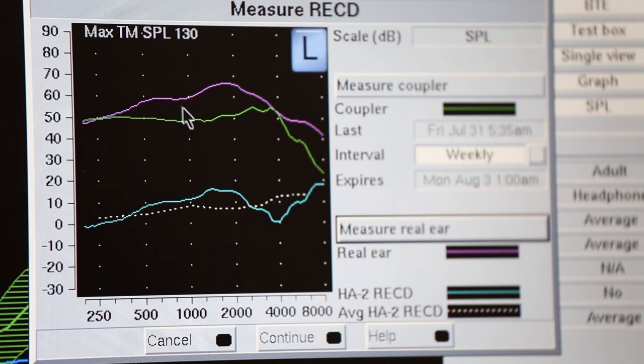You will often see that the real ear line is slightly above the coupler line. This will happen when the occluded ear canal space is smaller than 2cc, causing more natural amplification. That is, the 55dB sound being played by the speaker is naturally amplified and is louder at the ear canal. This will mean that the target will allocate less gain at these frequencies so that over amplification does not occur. The RECD results will now be used by the Verifit to calculate a target that is more specific to the client's real ear information.